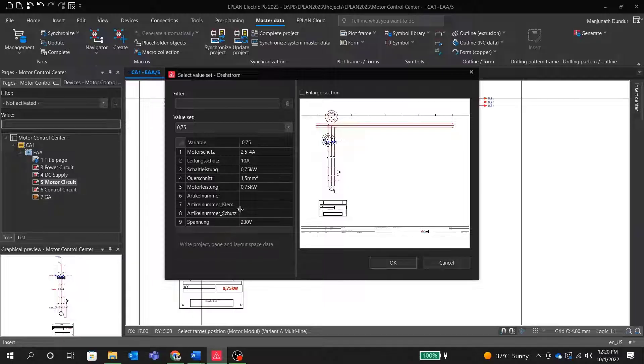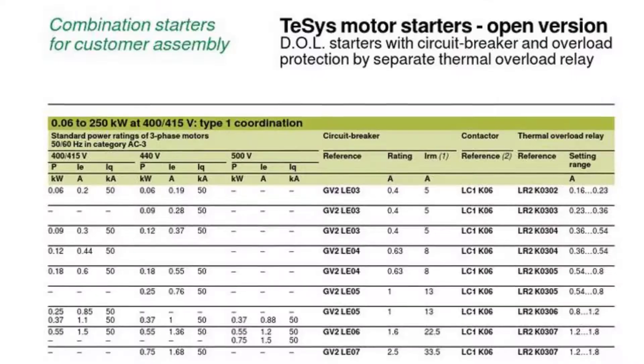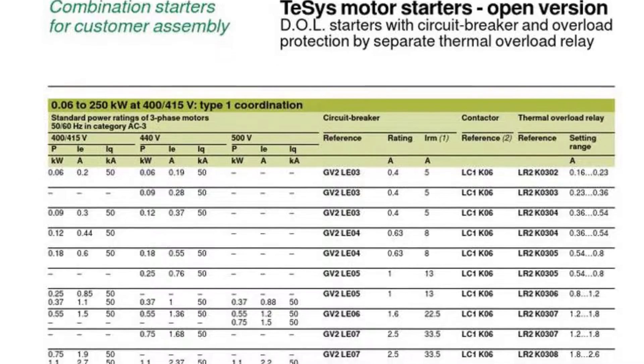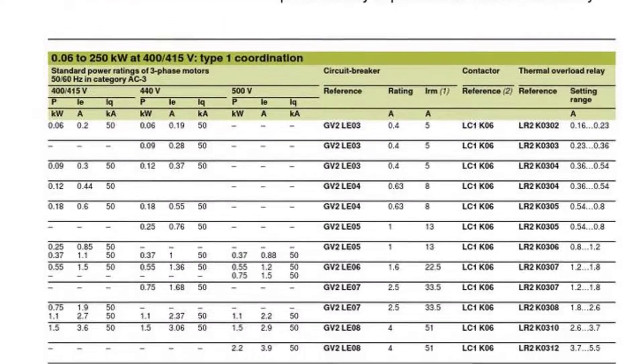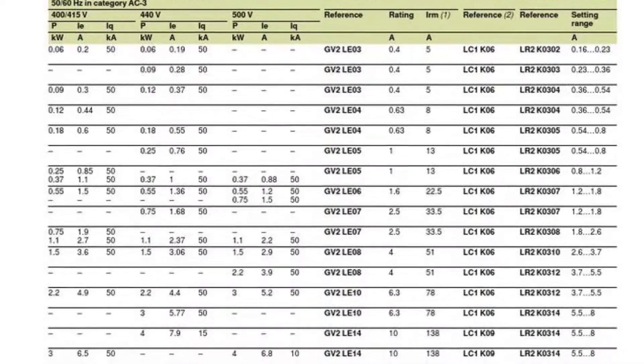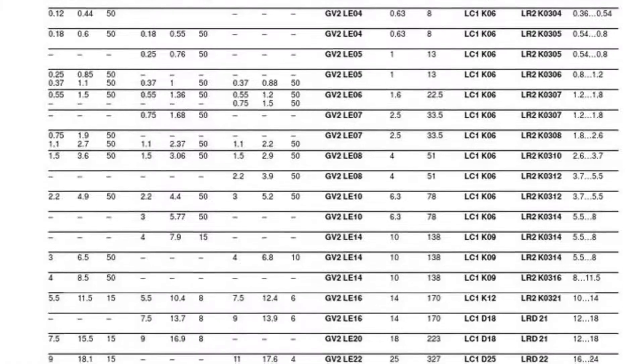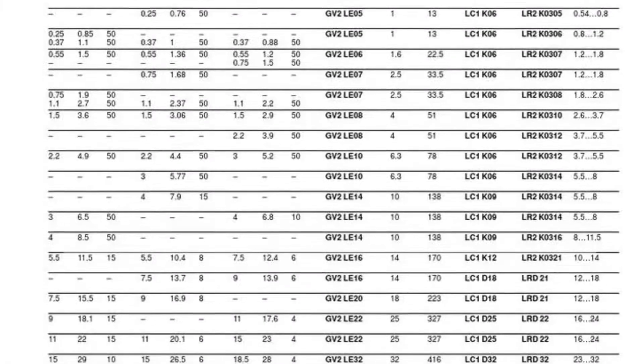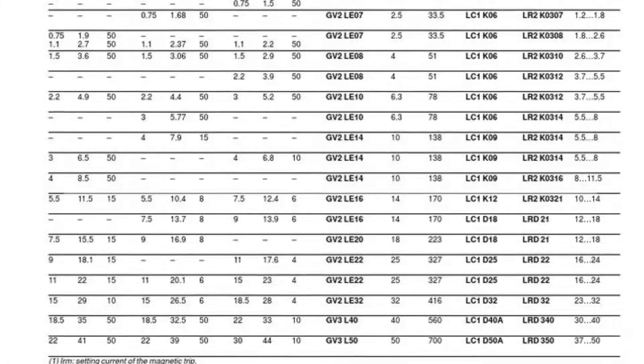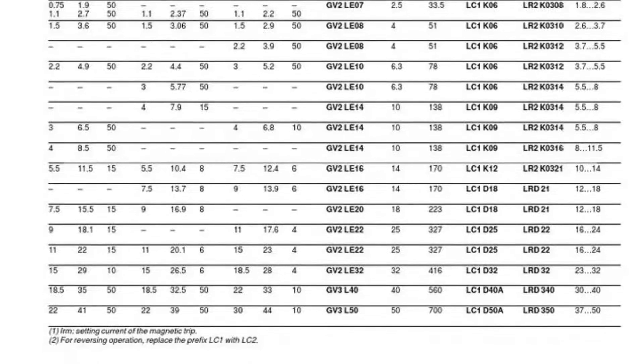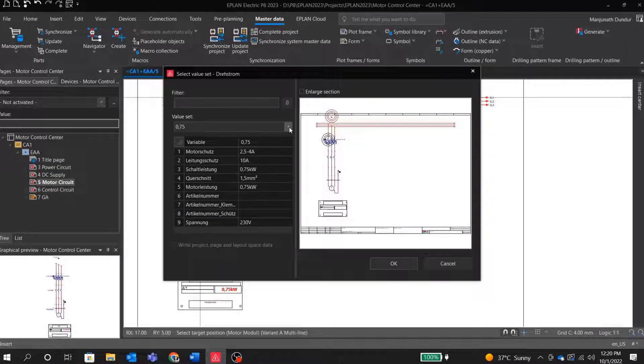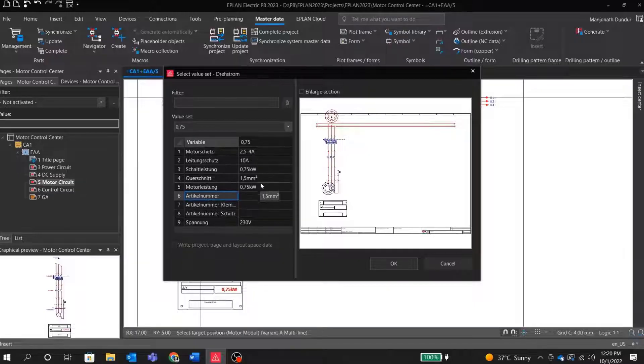We will select type 2 coordination table, which is provided by different vendors like ABB, Siemens, Schneider, etc. Let me explain what type 2 coordination is. Type 2 coordination requires that in a short circuit condition, the contactor or starter must not present any danger to the personnel or installations and must subsequently be able to resume operation. I am selecting 0.75 kW for a DOL starter here.